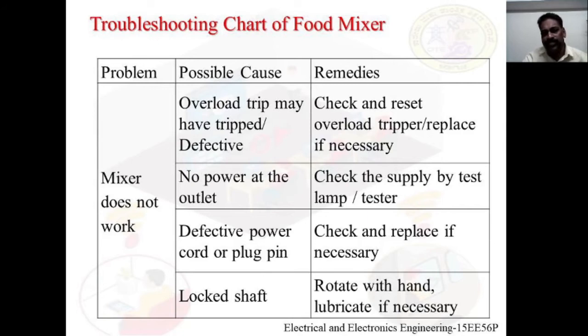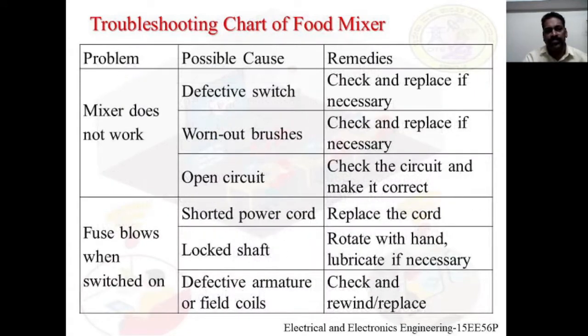Locked shaft. Rotate the shaft with hand and lubricate if necessary. Defective switch. Check the switch using a series test lamp and replace if necessary. Worn out brushes. Check and replace the brush if necessary. Open circuits. Check the circuit and make it correct.